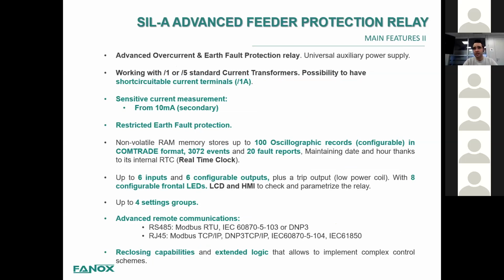This relay has a universal auxiliary power supply, and it works with 5 or 1 amps on the secondary, standard transformers again. We also have an option to have short-circuitable current terminals that work with a secondary of 1 amp. Despite it not being defined as a neutral or sensitive neutral on the relay, the measurement is so sensitive that we can measure from 10 milliamps on the secondary. So despite it not being defined like that, the sensitivity of the relay is very high. We also have, important for some applications, a restricted earth fault protection.